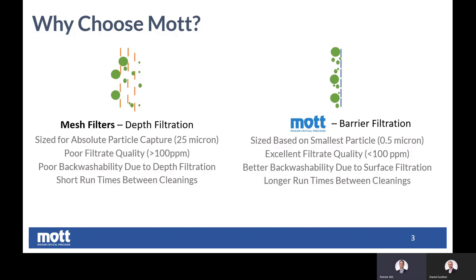What does that translate to? If you have better filtrate quality and better backwashability — keeping particles on the correct surface of the media — it means you're going to go longer between external cleanings. Your media is going to stay cleaner longer, you will have a more predictable recovery differential pressure, and because of that you should see the operation extended with a longer duration between those cleanings. And because you have a longer duration between cleanings, your system is online longer, your throughput is better, and you're spending less time doing maintenance.